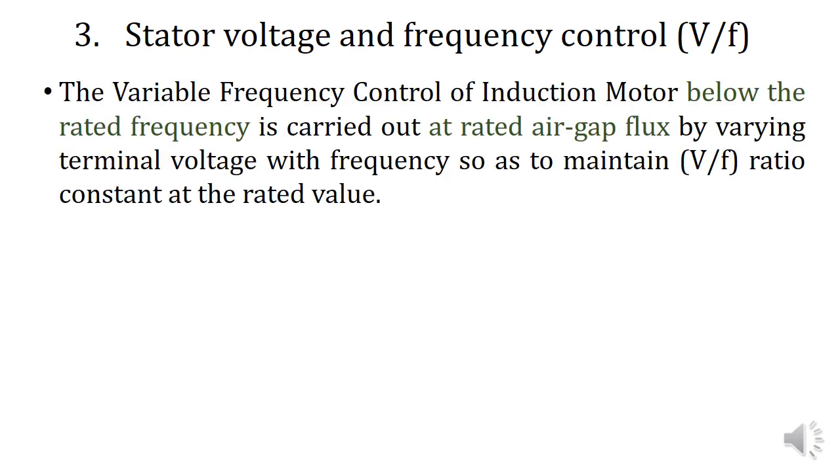The variable frequency control of induction motor below rated frequency is carried out at rated air gap flux by varying terminal voltage with frequency so as to maintain the V/F ratio constant at the rated value. Now let's see what are the effects of stator voltage and frequency control, that is V/F control, on the performance of an induction motor.